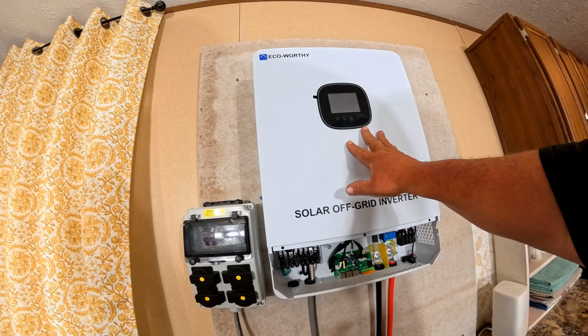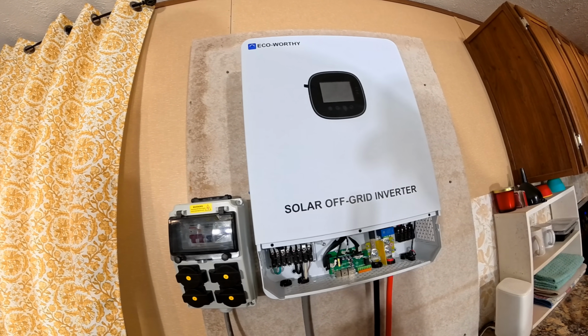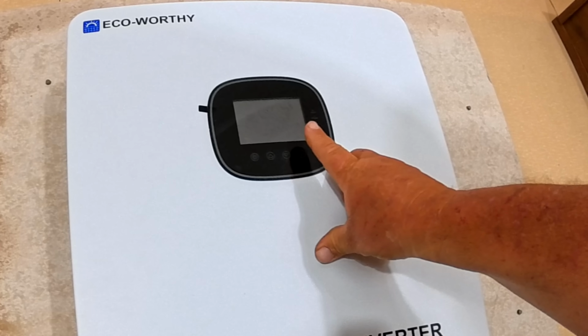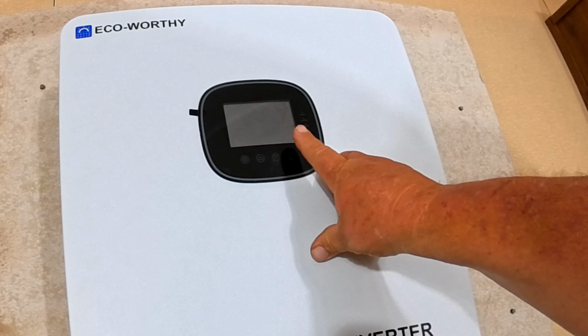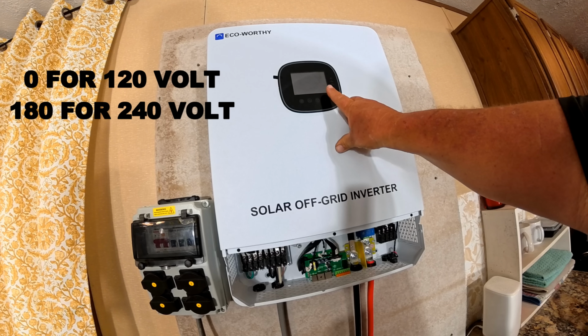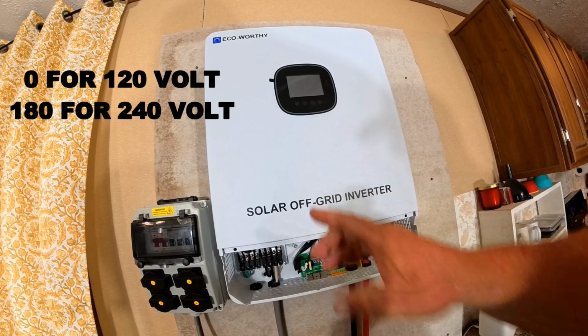It's going to throw a code on you as soon as you turn the inverter on. If you want it 240 volt, you have to go into setting 68 and change it from 0 to 180.